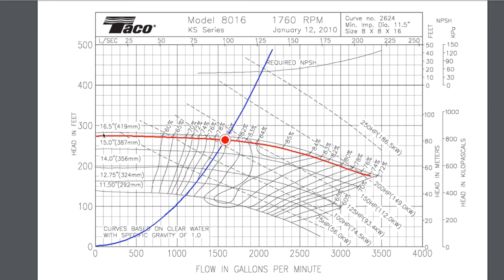The red line is just a little bit below the 16.5 inch line. What that tells us is that if we buy this pump with a 16.5 inch impeller, it will be milled down before delivery to a somewhat smaller diameter — probably about 16.25 inches. That means it'll operate at a slightly lower head output, and we won't need to put quite as much power in to drive the flow we're looking for.